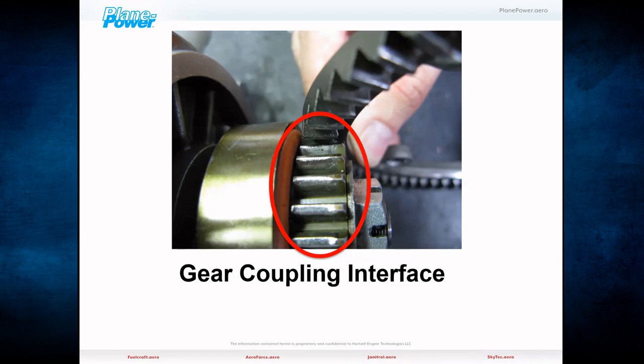You may push that coupling so far into the base gear that you get into the elastomer and start grinding it off, which dumps material into the oil system and can block oil passages. Also, pushing that coupling too far into the ring gear puts the rotor shaft in a bind and a bending moment, so every time it rotates, it's turning and bending. You know how long that's going to last—not very.